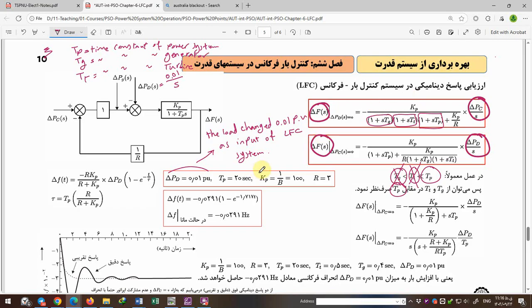Kp means B inverse is 100. The time constant of the power system is 20 seconds. Droop is 3. And so if you want to calculate the final value of delta F in changing delta PD.